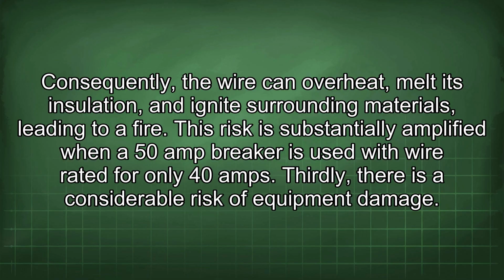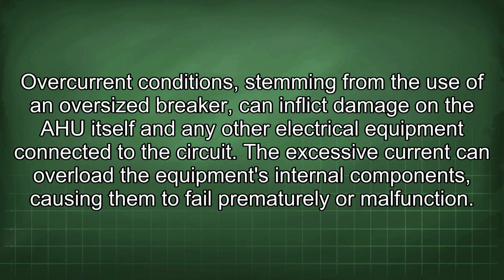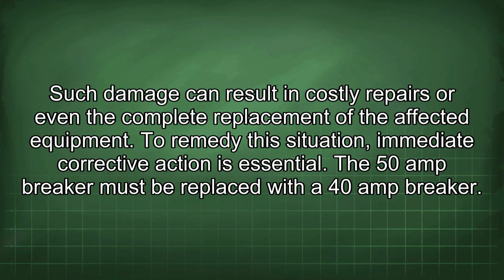Thirdly, there is a considerable risk of equipment damage. Overcurrent conditions stemming from the use of an oversized breaker can inflict damage on the AHU itself and any other electrical equipment connected to the circuit. The excessive current can overload the equipment's internal components, causing them to fail prematurely or malfunction. Such damage can result in costly repairs or even the complete replacement of the affected equipment.